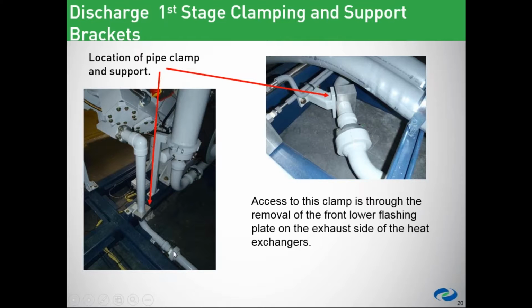And if we continue further and we go out to the front, or not the front, but the discharge louvers, and open those doors, we cannot physically see this next clamp. You would have to remove the lower flashing piece, which is the same stuff you would remove for the heat exchanger changeout. So just the lower piece, and then you'll be able to see this clamp inside of that opening, and it's easy access to get in here and take this apart. So if you ever have to work on that, basically that train of piping, this is how we would do it.